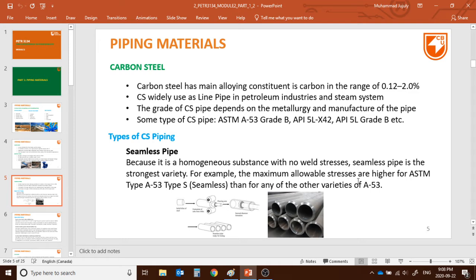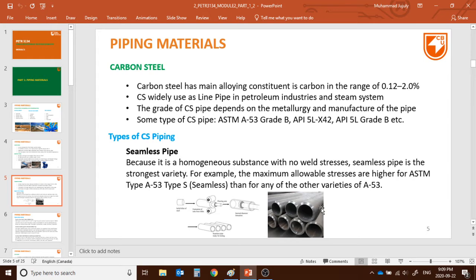For example, the maximum allowable stress is higher for ASTM A53 Type S — and Type S means seamless. The seamless pipe gets the highest allowable stress, lower weld stress (actually no weld stress at all), and a lower chance of corrosion attack. It's the perfect variety. However, one problem with seamless is we can't make it very large — for instance, a four-foot diameter seamless pipeline is very expensive to manufacture.